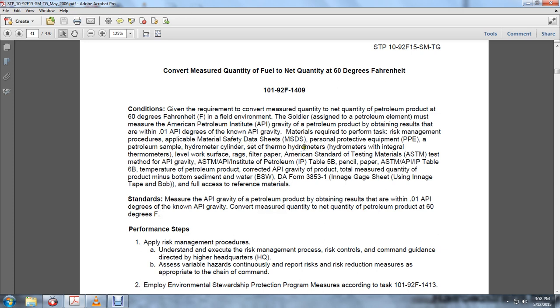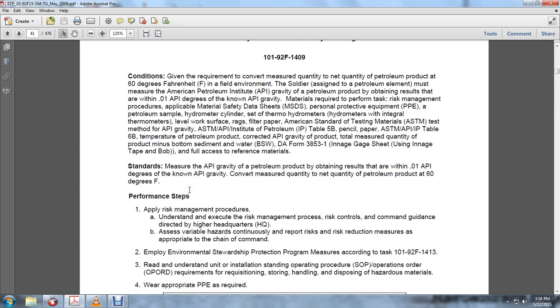hydrometer cylinder, the set of hydrometers, integral hydrometers, level work surface, rags, filters, American standards, testing materials, testing methods of API gravity, ASTM, API, Institute of Petroleum, Table 5 and Table 6B, temperature of the petroleum product corrected by the API gravity of the product, total measured quantity of products, the minus bottom sediment and water, BS&W, DA Form 3853 innage gauge sheet, using the innage gauge tape and bob, and full access to the reference materials. Measuring the API gravity of the petroleum product, obtaining results within 0.1 of an API degree, known as the API gravity, converts the measured quantity to the quantity of the petroleum product at 60 degrees Fahrenheit.